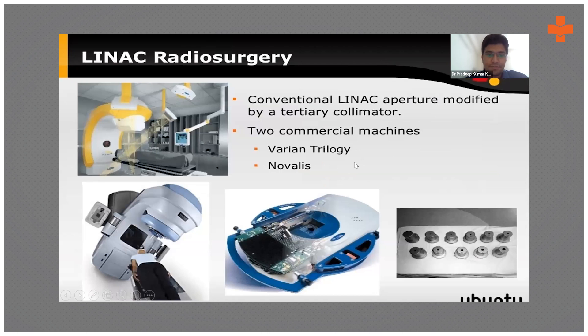This is a linear accelerator adapted to deliver radiosurgery capabilities. Sometimes the BrainLab system is used for radiation to CNS tumors, and it can precisely deliver a high amount of radiation in a short amount of time. These are optimizations done to a linac to enable these capabilities — not all linear accelerators can do this; they require specific capable equipment.